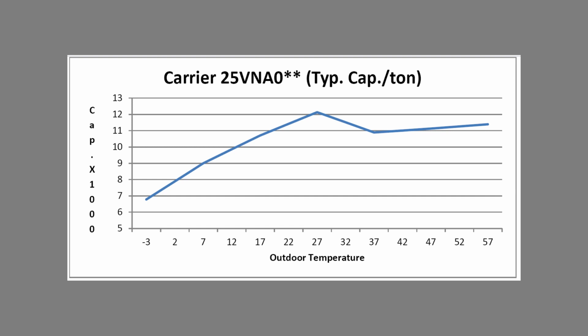Now with inverter-driven systems and cold climate systems, we can see the lines aren't quite the same anymore. This particular system, and it's a Carrier system, its peak capacity is at roughly 25 degrees, which is a pretty nice fit. And you can see it's actually got greater capacity at 25 than it does at 52. And that makes sense. Our houses don't need to have the full capacity of the heat pump running when it's warm outside. And then we have that typical sort of capacity decline, but rather than starting at 60 degrees, it starts around 25 degrees and goes down.